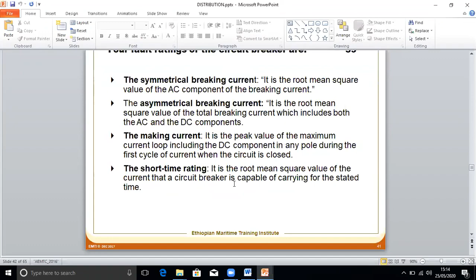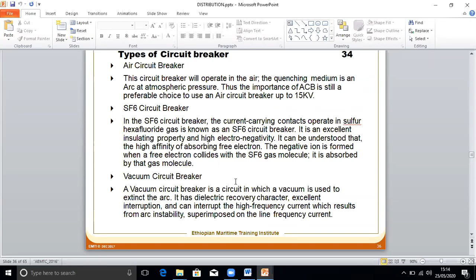So we have seen these three types of circuit breakers: air circuit breaker, SF6 breaker, vacuum circuit breaker. The difference is in the media in which the contacts are operating. In an air circuit breaker, the fixed and moving contacts of a breaker are moving in atmospheric pressure. SF6 is using SF6 gas. Vacuum circuit breaker is moving in the vacuum. This is the difference.